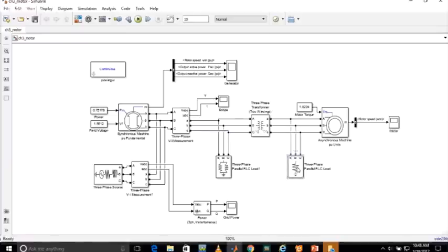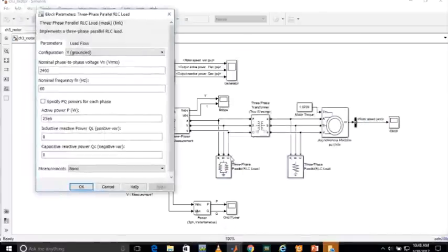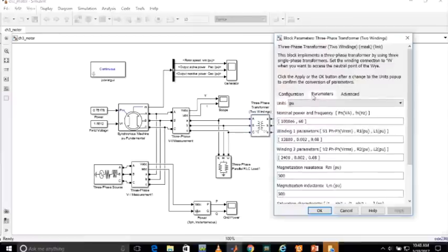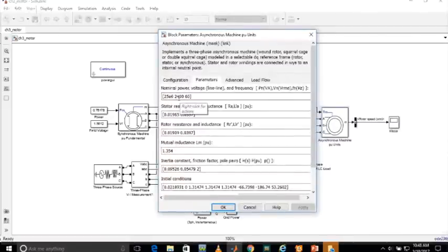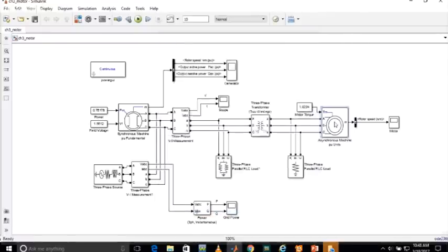So again, in this circuit, if you check, the parallel R branch is of 25 megawatt type, but its voltage is 2400 volt because we have connected a transformer with parameters 13.8 kilovolt to 2400 volt. Similarly, these parameters are also 2400 volt and 25 megawatt type. As you will see, this machine requires 25 megawatt, this R load provides 25 megawatt, and this RLC load needs 40 megawatt and 15 MVAR reactive power.